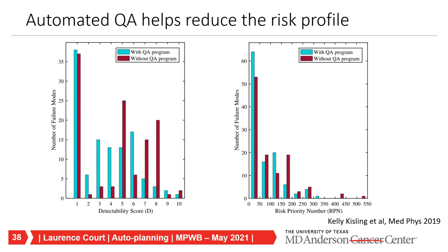A slide from Kelly Kisling shows the impact of introducing automated QA into an automated workflow. If you have something like the RPA doing automatic contouring and planning, and then add automated QA to verify plans and contours, what's the impact on the risk profile? The figure on the left shows the number of failure modes by detectability score—a score of one means very detectable, hence low risk. Without the QA program, there are quite a few high detectability scores (hard to catch). With the QA program, that goes down, and the number of high risk priority numbers also decreases significantly.